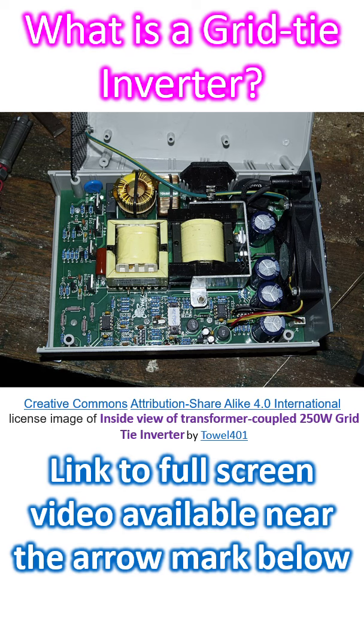Transformer-less inverters need galvanic isolation between the DC side and the AC side. Otherwise, dangerous DC voltage can reach the grid under fault conditions. This mandates additional safety measures to be implemented for preventing this.